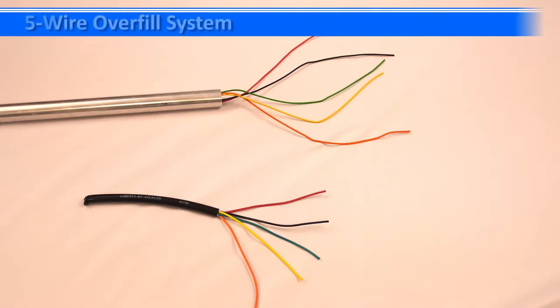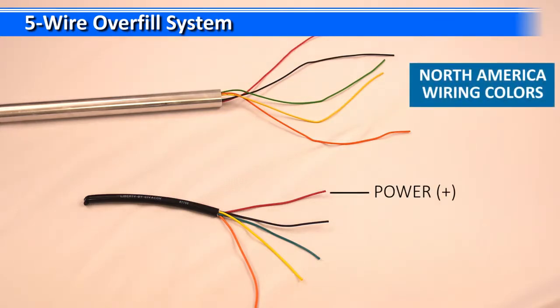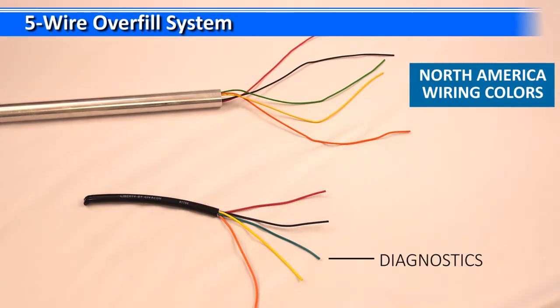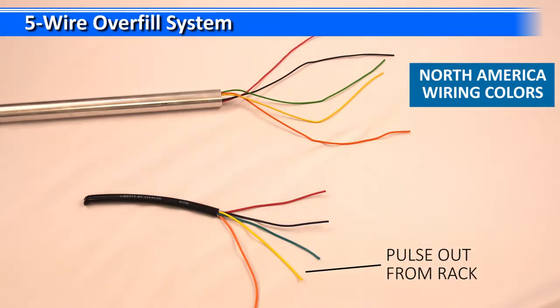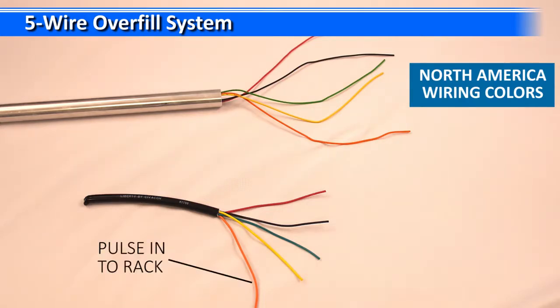Here we have an example of a 5-wire overfill probe and the 5-wire main cable coming from the socket. We're going to quickly touch on the different wire colors and what they do. The red wire is your positive power wire. The black wire is your ground. The green wire is a common diagnostics line. The yellow is the signal from the rack, the pulse out from the rack, and the orange is the pulse back into the rack.